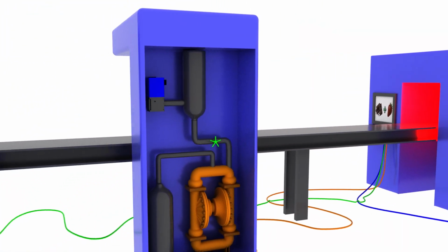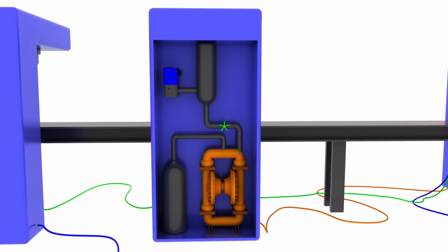In this automated frosting dispensing process, one tank is filled with frosting. An air-operated diaphragm pump fills the second tank that will dispense the frosting onto the product. As the first tank empties, the system alternates between the two with the help of a solenoid valve to keep production moving continuously.